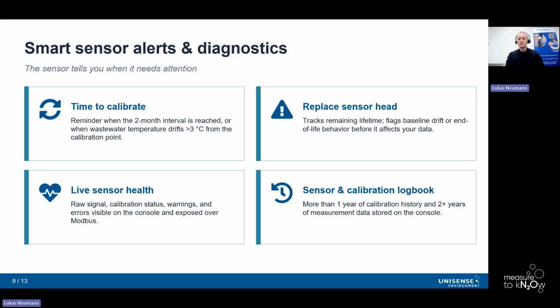Then in terms of sensor and calibration logbook, we have 1 year calibration history, 2 years of measurement data saved on the console, which is good for traceability and reporting. The key point here being that this system then turns your nitrous oxide monitoring from another thing to manage to a set and forget instrument that notifies you when it needs you.